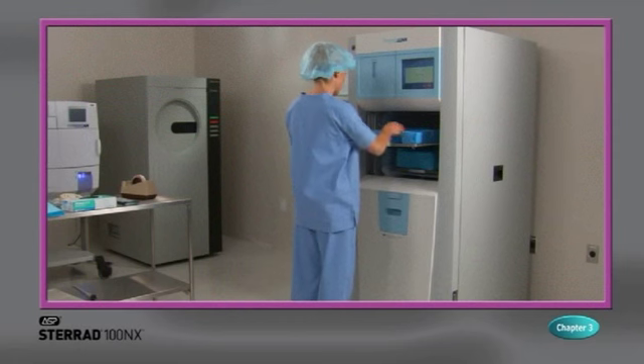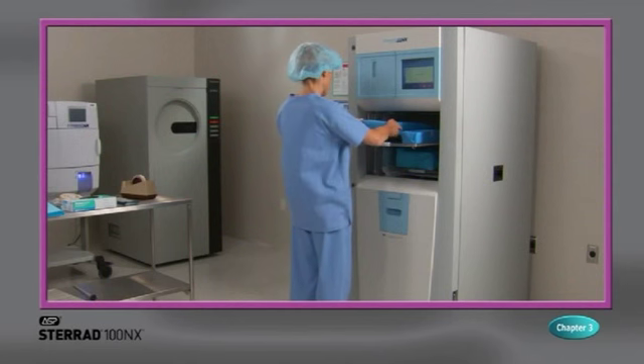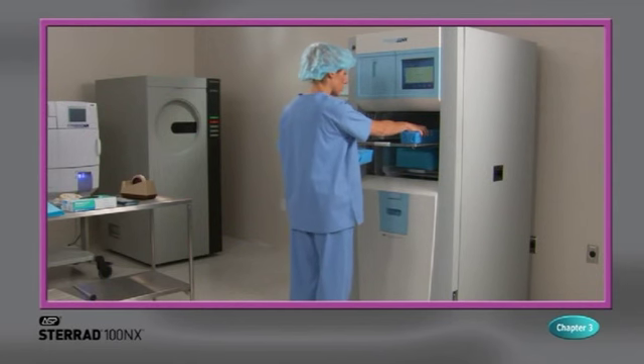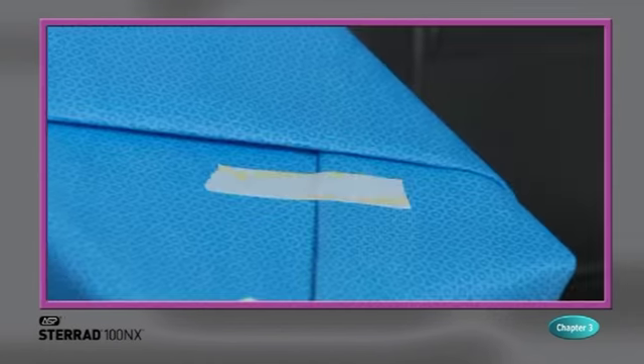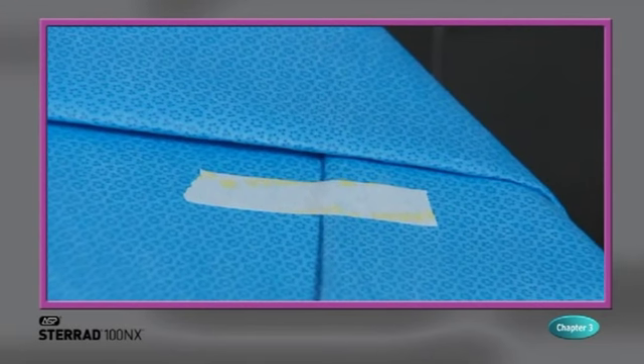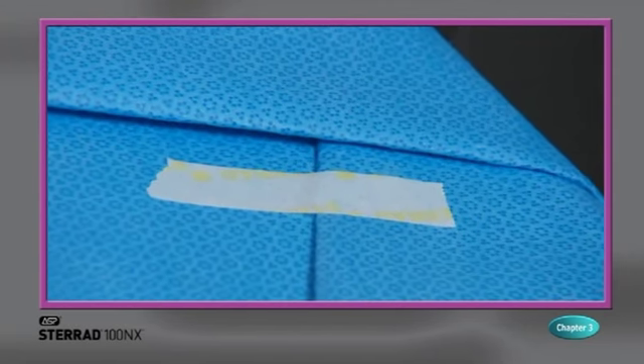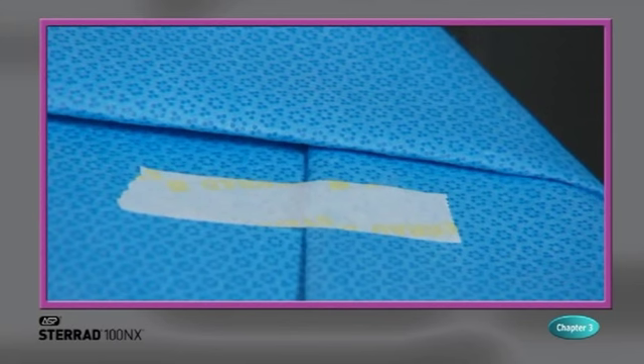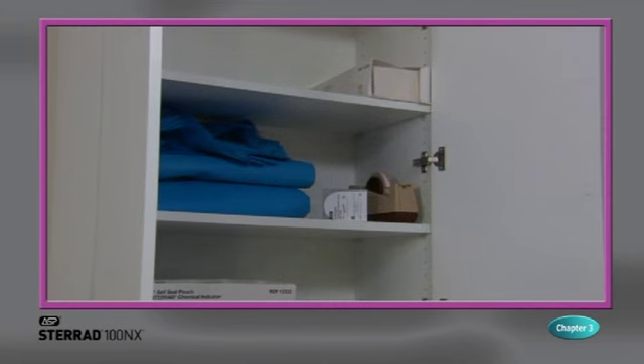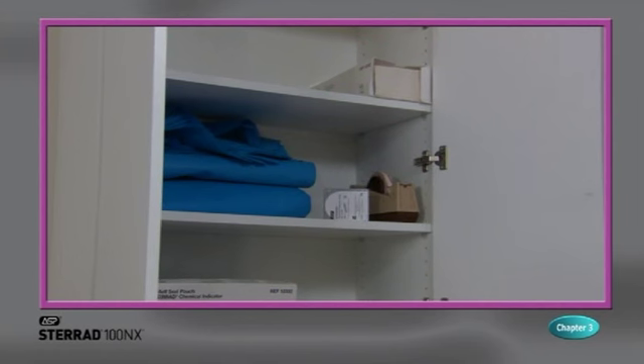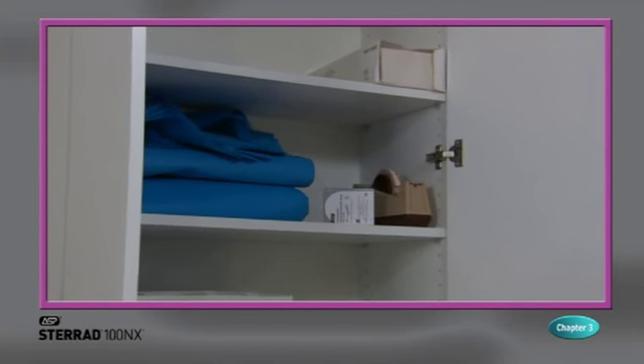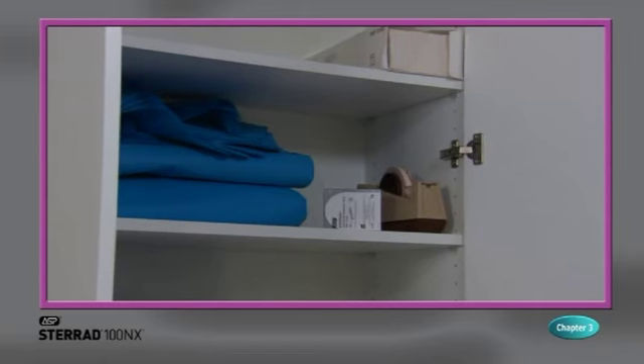Please note that the primary purpose of the Sterrad SealSure chemical indicator tape and the Sterrad chemical indicator strips is to verify that the load has been exposed to hydrogen peroxide. Chemical indicators are not a substitute for biological indicators. Make sure that chemical indicator strips and chemical indicator tape are stored away from light, as they will change color from red to golden yellow if exposed to light. Please follow the instructions for use that accompany the chemical indicators as you prepare the load.